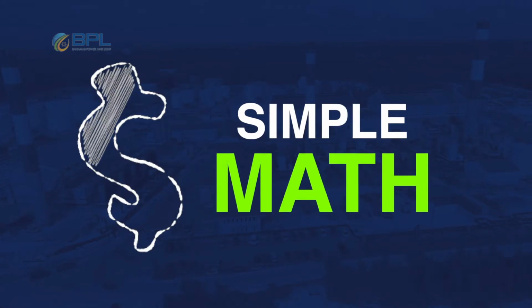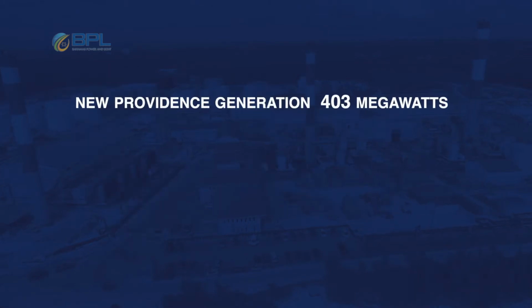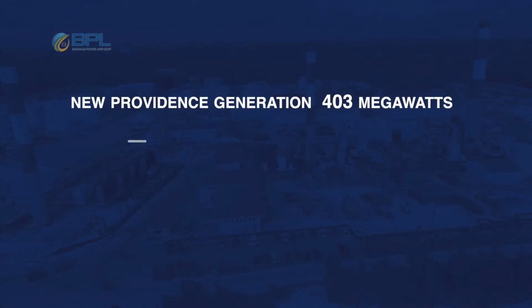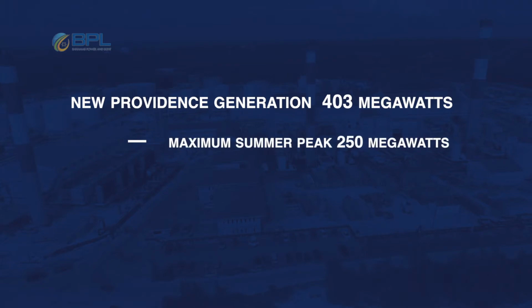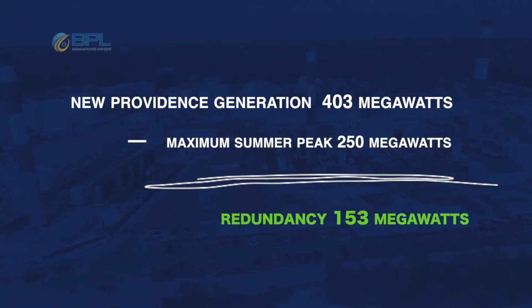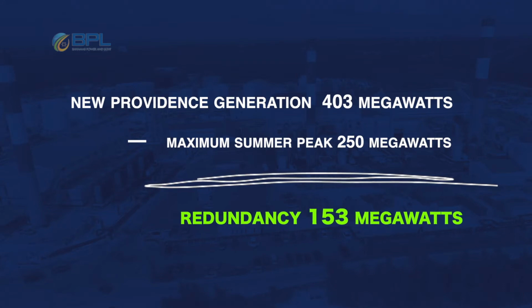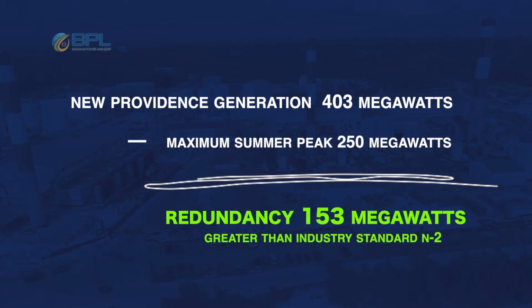So the simple math is this: New Providence generation at 403 megawatts minus a maximum peak of 250 megawatts means we have a redundancy in generation of 153 megawatts, which is greater than industry standard N-2.